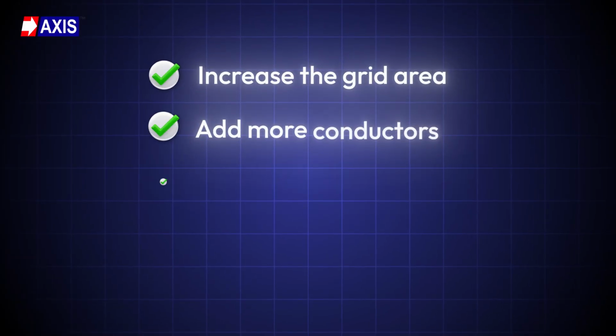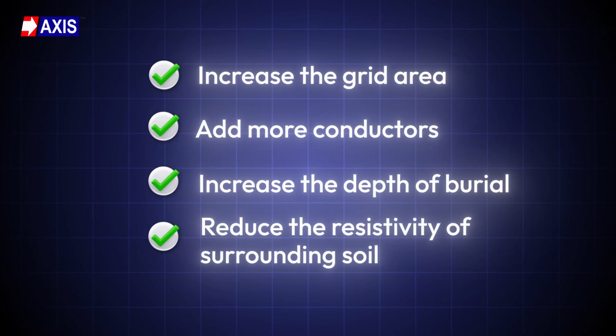If grid impedance is too high, GPR rises to dangerous levels during a fault, leading to hazardous touch and step potentials across the yard. A high grid impedance also causes uneven distribution of fault current, with high current densities concentrated near the fault location, resulting in localized heating and damage to the grid itself. To reduce grid impedance, increase the grid area, add more conductors, increase the depth of burial, or reduce the resistivity of the surrounding soil. All of these measures lower the opposition the grid offers to the fault current, keeping GPR within safe limits. Now that you understand the risks, let's look at how a substation earthing system is actually designed.